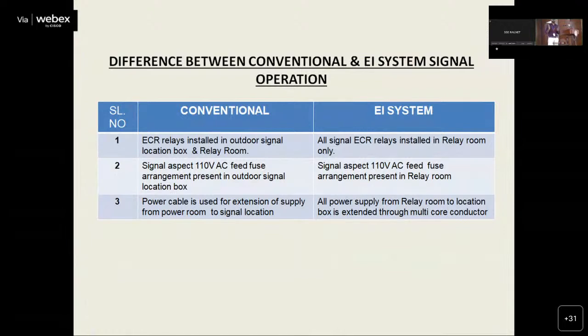Regarding signal operation, all the ECR relays are now available in the relay room itself. Whatever supply we send to the signal, after proving all things, we directly send it from the relay room to the outdoor location itself. We are not keeping ECRs in outdoor locations anymore. Apart from that, in the new system, whatever supply we send is through multi-core cable only; we are not utilizing any power cable. All power cables have been abandoned nowadays.